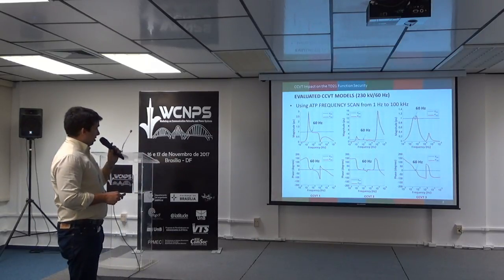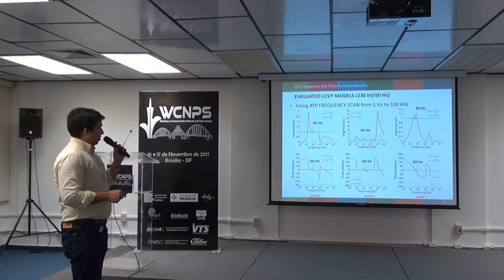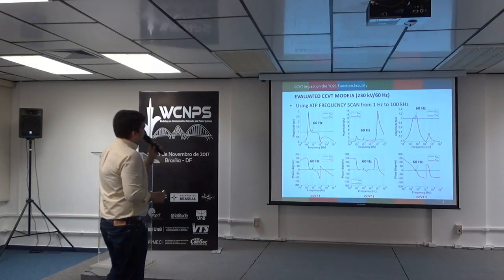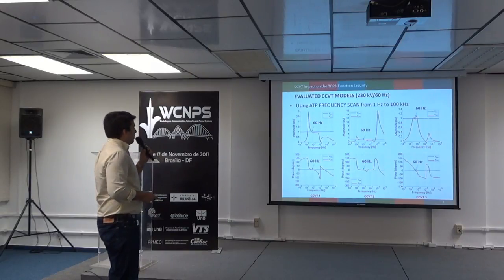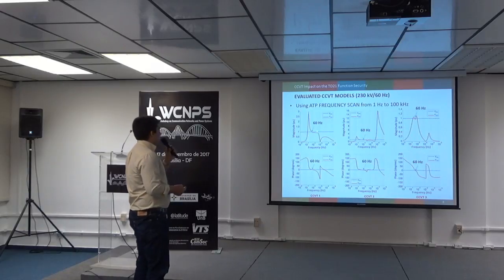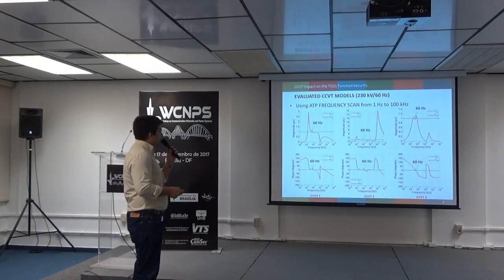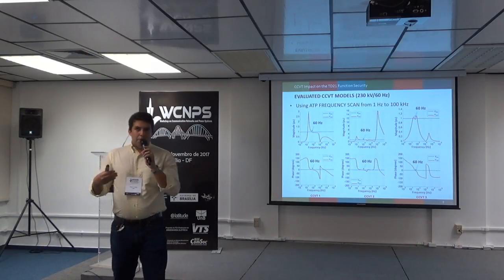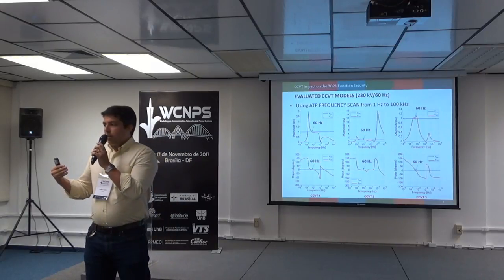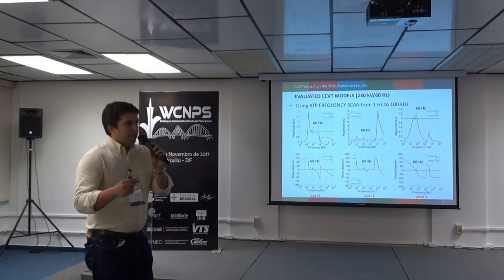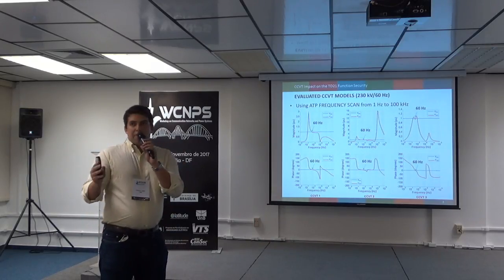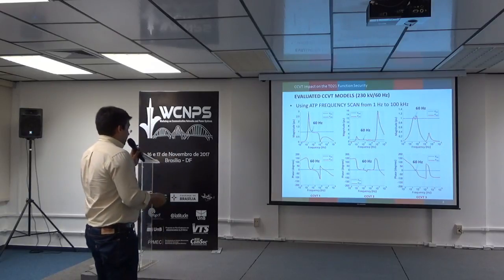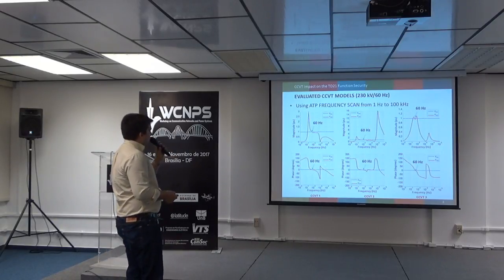All these CCVT models have a rated voltage of 230 kV and operate at 60 Hertz. As we can see in this figure, we have only the expected response at the fundamental frequency of the system, in this case 60 Hertz. We have to understand the expected operation of this equipment as 1 pu of magnitude and 0 degrees of phase angle, because we have to have a unit gain without phase displacements. So if some transient components show up in my signal, they will not be properly represented in our secondary winding signal.